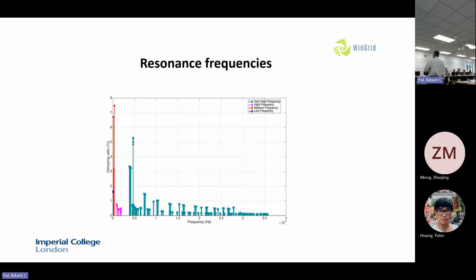Now, I want to address a misconception about harmonic instability. Most of the time, these terms are well known in the power electronics community as harmonic instability. But to call it harmonic instability, the frequency must match multiple times of a certain fundamental, like 50, 100, 150, and so on. Here, what is happening, I don't want to call it harmonic instability—I want to call it resonance, because the network itself has inductance, capacitance, and various controls.